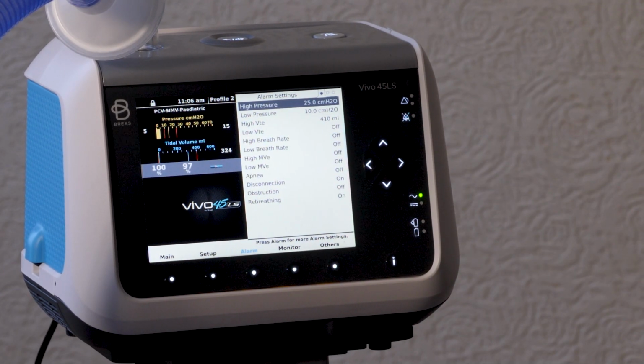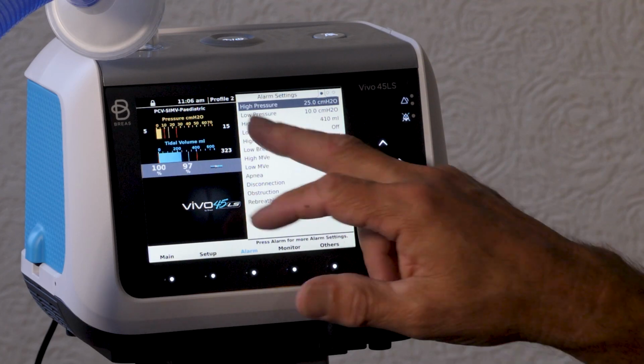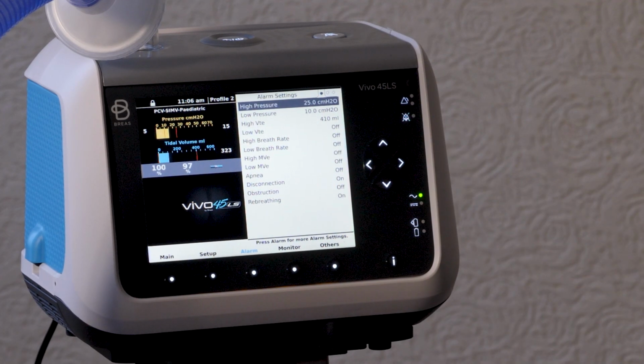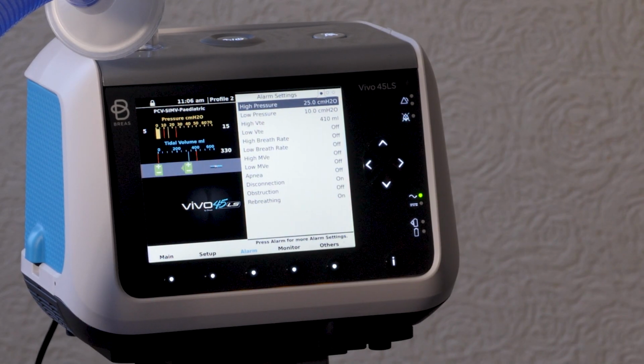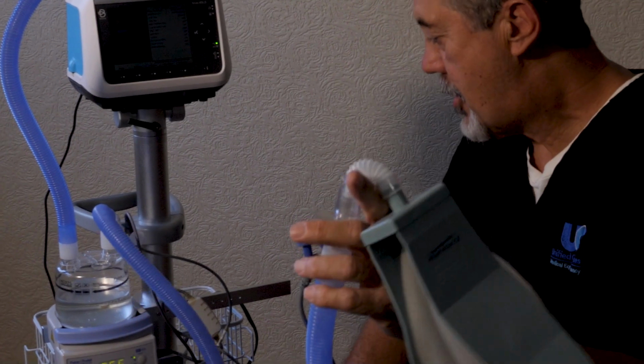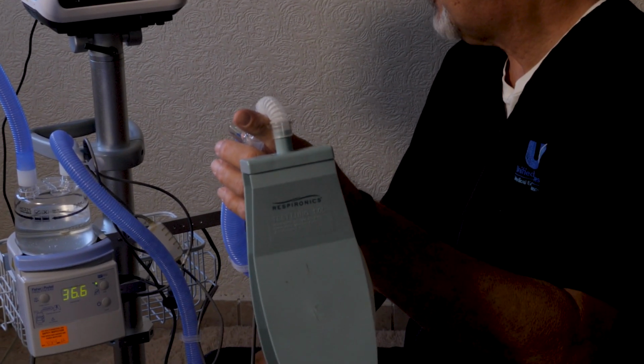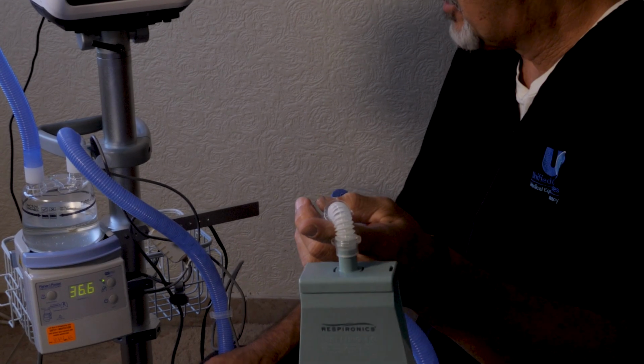Otherwise, if you're suctioning the patient and you're able to suction out a good amount of secretions and now this alarm quits sounding, you resolve the alarm. Another possible cause for a high pressure alarm could be water in the tubing. Okay, so if you have a lot of excess water in the tubing, and typically the way that works is the tubing comes down and then back up. So you might have water accumulated at the bottom of the tubing here. If that's the case, you want to drain the water out.